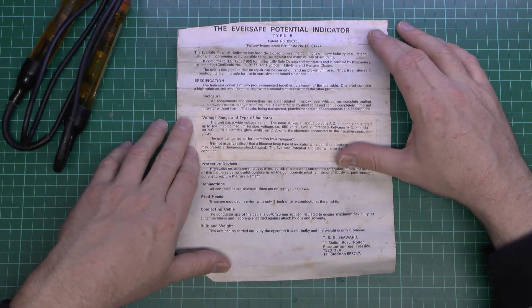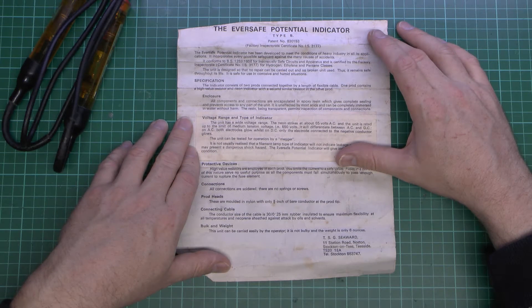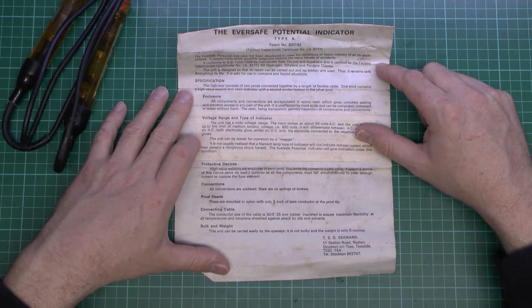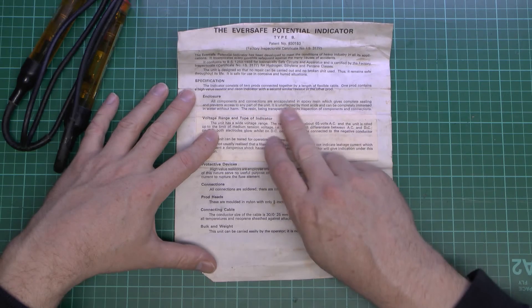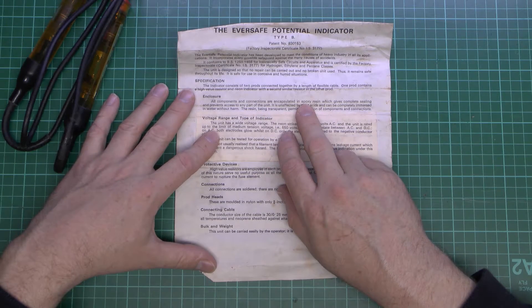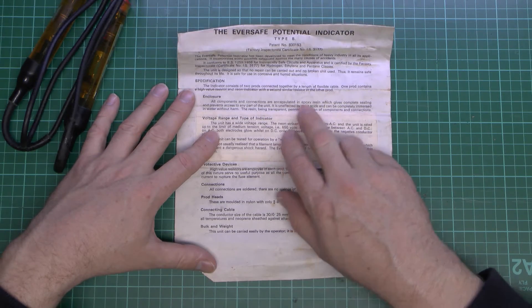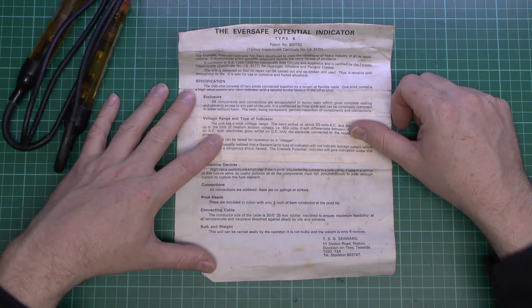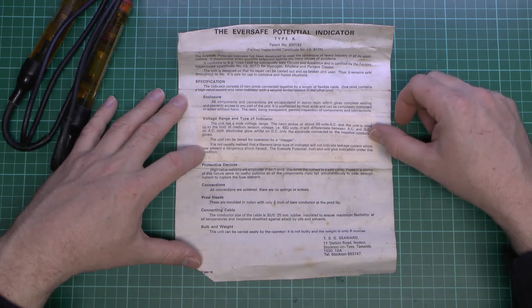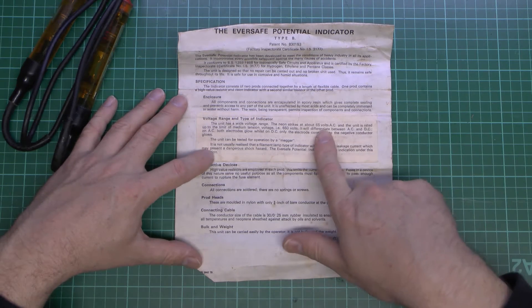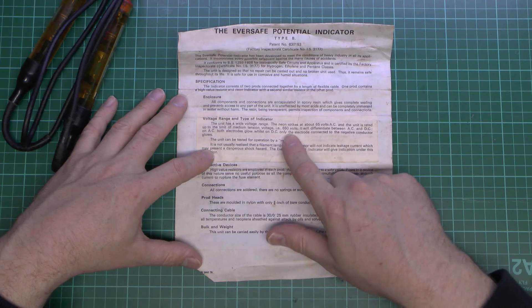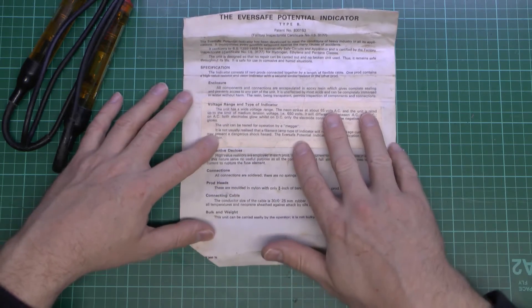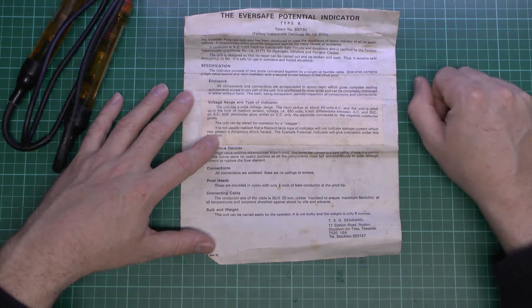Essentially it's a two-pole device, contains a neon indicator inside, and it's also got the resistors in there to limit the current. It's enclosed in epoxy resin, so the whole thing is totally potted in there and sealed, so it won't have any danger of getting water and other contaminants inside. It works from about 65 volts AC and goes up to around 650 volts. Notice it's called medium voltage there, that's not the correct term anymore, but of course it was when this was actually made.